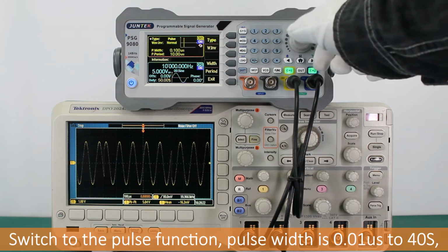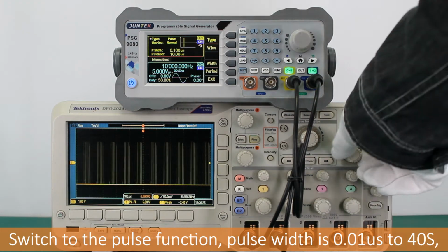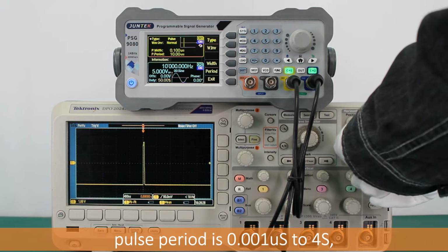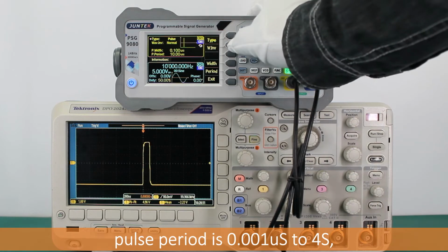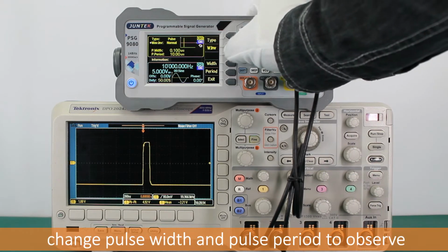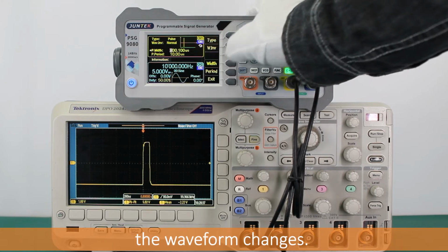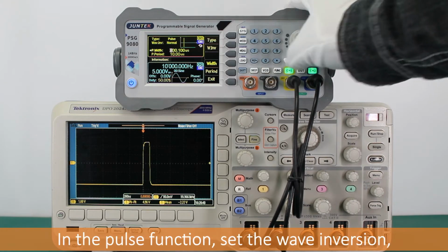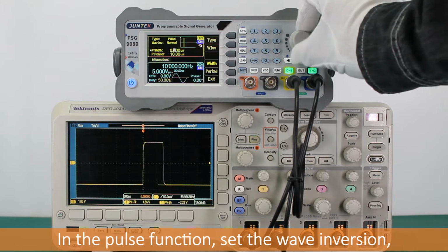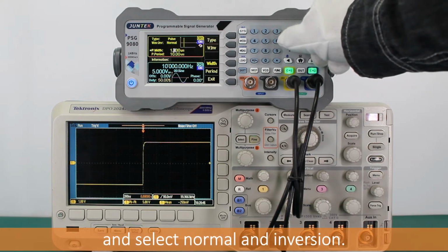Switch to the pulse function, pulse width is 0.01 us to 40s, pulse period is 0.001 us to 4s, change pulse width and pulse period to observe the waveform changes. In the pulse function, set the wave inversion, and select normal and inversion.